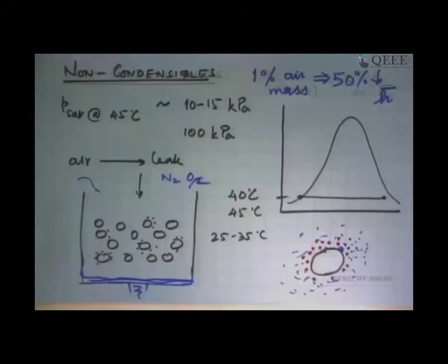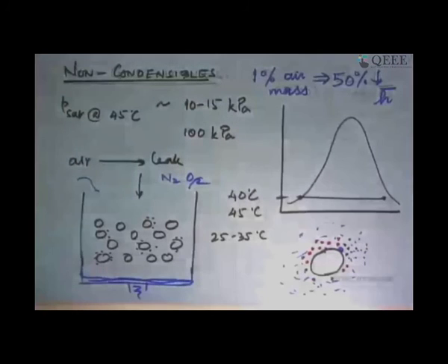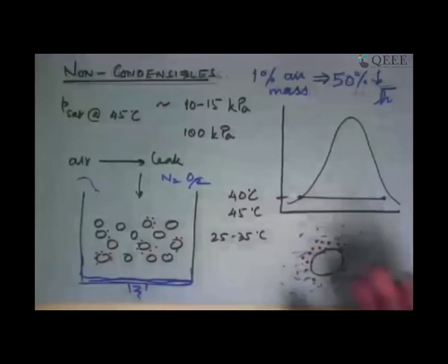That is a huge penalty, which means that you cannot condense that much steam, which means that the whole cycle cannot generate as much. You have decreased the heat transfer coefficient by 50%, condensation rate goes down by 50%, the generating capacity of the whole power station goes down by 50%. That's a huge loss. So what do we do? So what engineers do is that we cannot make a 100% leak-proof machine anyway. So in the condenser, the tubes are arranged in a certain way so that you give path.